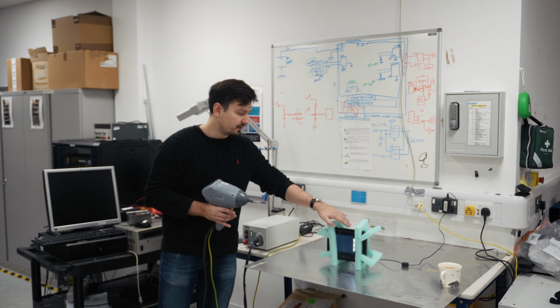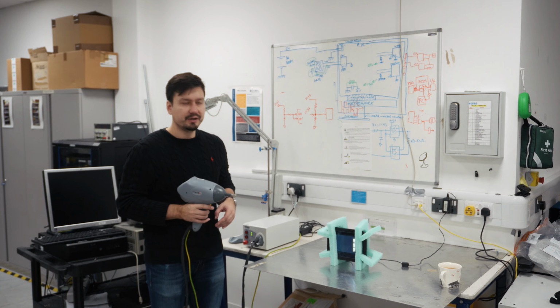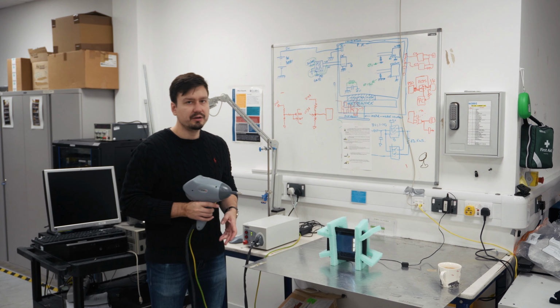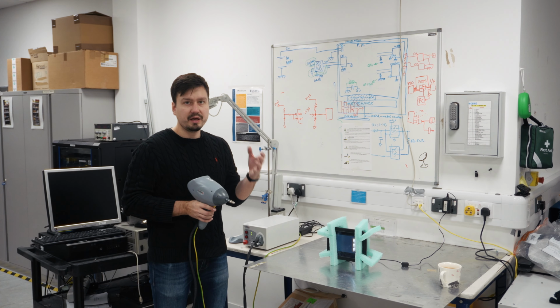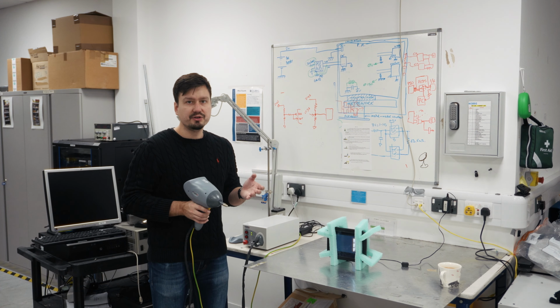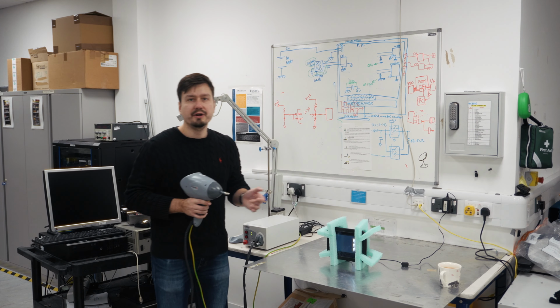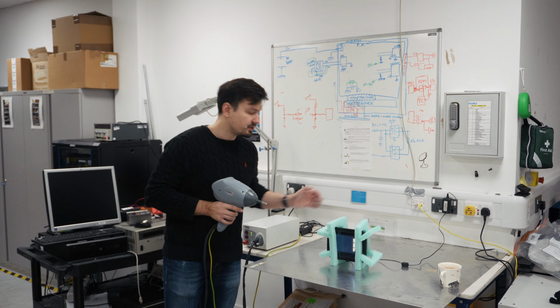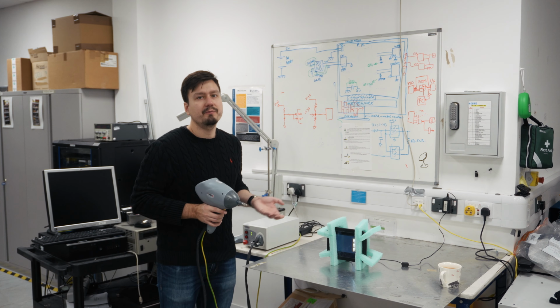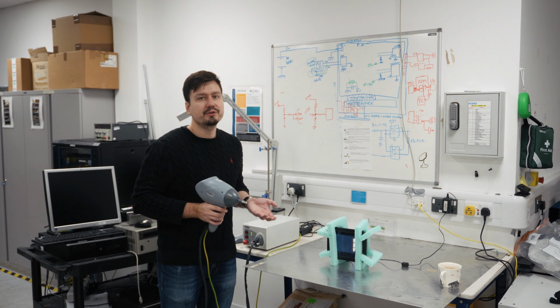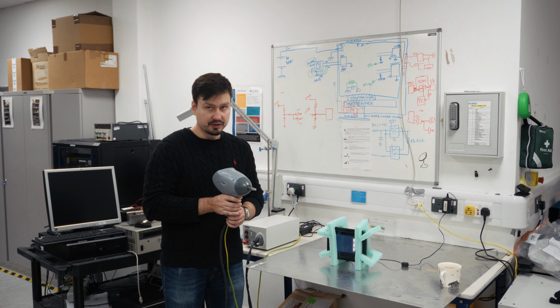It has a really thick glass protector and a very thick plastic cover, and remember, we only apply air discharge to areas where there's no metal. So I'm not going to apply it in the area I showed you earlier for contact discharge because it will obviously discharge into metal, but we're looking to see if it discharges through the plastic, and that's the point of the air discharge.